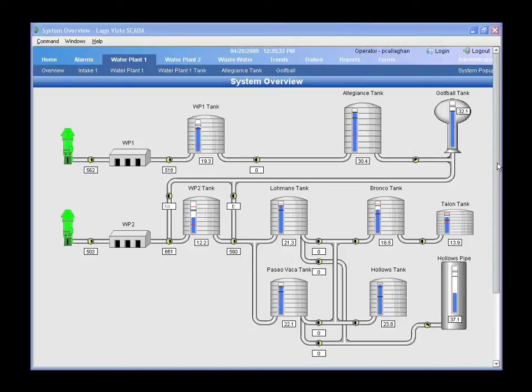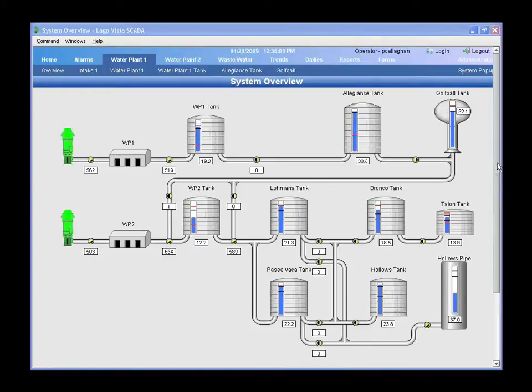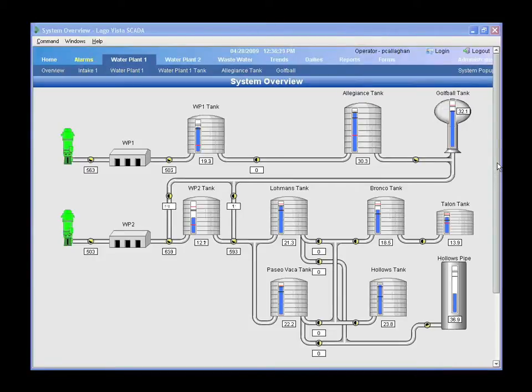One of the major issues was the licensing that Wonderware puts out and the cost — not only for the end user, but for me as a system integrator. I had to pay Wonderware every year just to be an authorized system integrator. We ended up choosing Inductive Automation. We networked three plants together with fiber optic, added a VPN and connected to the Internet. Now the operators all have tablet PCs — they connect to the Internet through their cell phone, VPN into the network, and operate the SCADA system as if they were at a local computer.